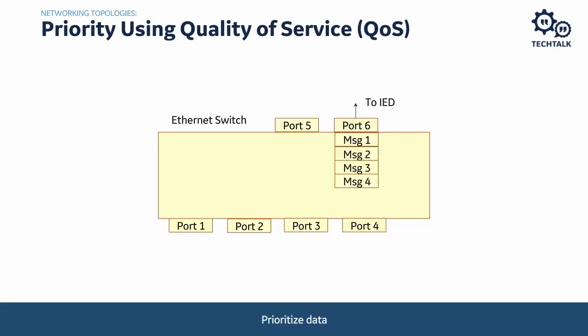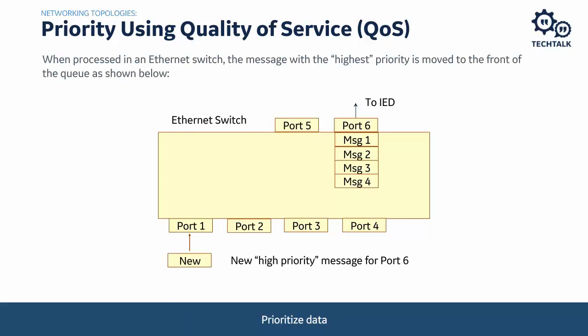Not all data are created equal — certain data are more critical than others. For example, a time-sensitive peer-to-peer GOOSE message must have priority over non-critical data. Typically in a switch, when data reaches a port and needs to be forwarded, it ends up in a queue because a port may not have enough bandwidth to handle all messages simultaneously. With quality of service (QoS), it gives the message a priority. If a message with high quality of service comes in, it gets bumped to the top of the queue and is sent over non-critical messages.